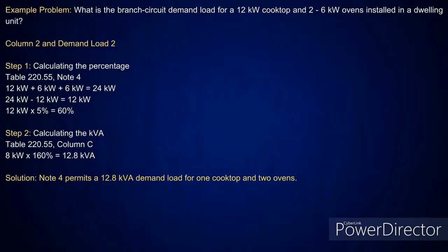Now, here's a good one of unequal ratings, and this is where you want to get into this and look at note 4. Now, I have a 12 kW cooktop, and I got 2 6 kW ovens here. I'm going to do pretty much the exact same thing. I'm going to add them up, and remember, I'm treating this as one unit because if you look, I'm telling you I have a branch circuit here.